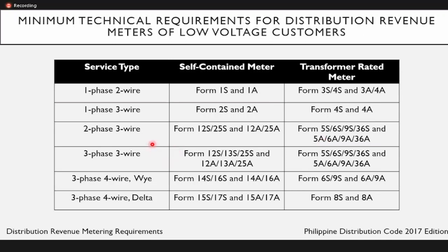For the two-phase three-wire, the self-contained meter should be form 12S, 25S, and 12A, 25A. For the transformer rated meter, it should be form 5S, 6S, 9S, 36S, and 5A, 6A, 9A, 36A. For the three-phase three-wire, the self-contained meter should be form 12S, 13S, 25S, and 12A, 13A, 25A. For the transformer rated meter, it should be form 5S, 6S, 9S, 36S, and 5A, 6A, 9A, 36A.